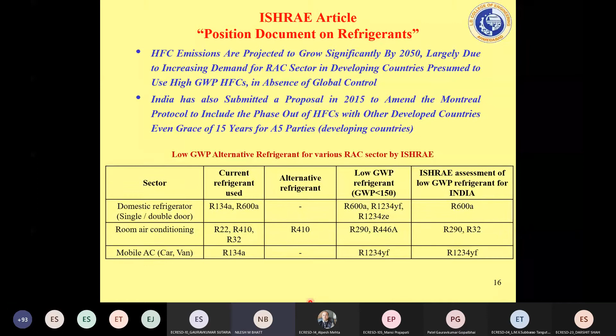The reason is very obvious: in a mobile air conditioner, the refrigeration system is operated very close to the high temperature engine, and R600a is very flammable. You know that it's a hydrocarbon, and hydrocarbons are very flammable. So because of the safety issue, ISHRAE has proposed the completely non-flammable or less flammable refrigerant R1234yf in the mobile air conditioner, while based on the charge quantity and the leak-proof system, ISHRAE recommended R600a for the domestic refrigerator.